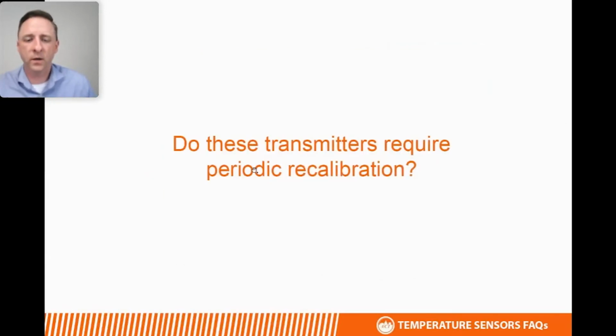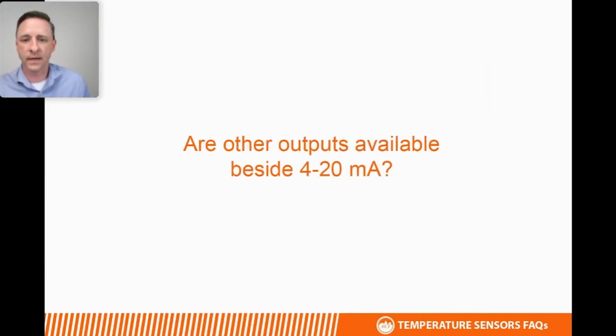Do these transmitters require periodic recalibration? We do not have a standard or recommended calibration interval. There are a number of applications that require recalibration, and we leave that up to the requirements of the specific job or application. We do offer recalibration and recertification services. Any of our transmitters, which are 4 to 20, 1 to 5, or 2 to 10 output devices, can be sent back to us for periodic recalibration or recertification. There is a small fee charged for that service, but it can be done at any time.